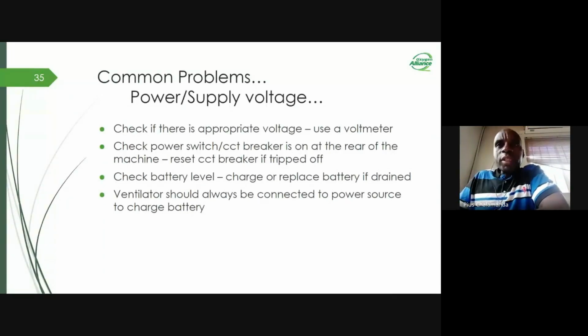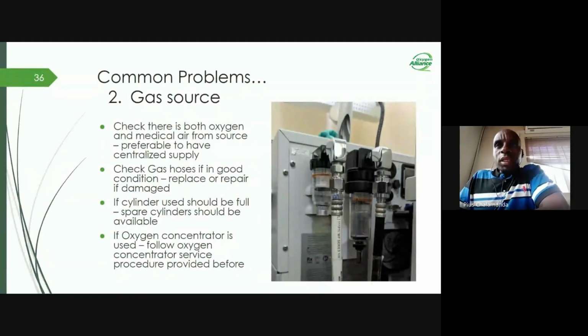Okay, so let's continue looking at the common problems of ventilators. This time around, we'll look at the gas source. You need to check if both oxygen and medical air are available from source. Preferably, we use centralized supply, but in case you don't have centralized supply, you may use an oxygen cylinder or an oxygen concentrator to provide the oxygen source, or you may use a compressor to generate medical air. You can also check if the gas hoses are in good condition. You may replace them if damaged, or you can repair them.